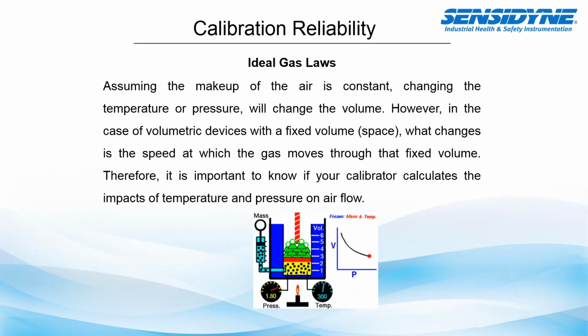Assuming the makeup of air is constant, changing the temperature or pressure will change the volume. However, in the case of volumetric devices with a fixed volume or space, such as a calibrator, what changes is the speed at which the gas moves through that fixed volume. Therefore, it is important to know if your calibrator calculates impacts of temperature and pressure on airflow.